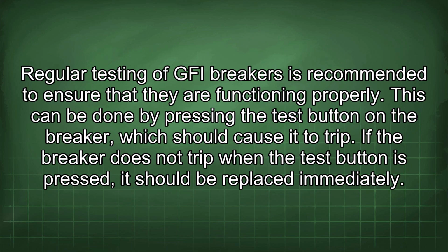Regular testing of GFI breakers is recommended to ensure that they are functioning properly. This can be done by pressing the test button on the breaker, which should cause it to trip. If the breaker does not trip when the test button is pressed, it should be replaced immediately.